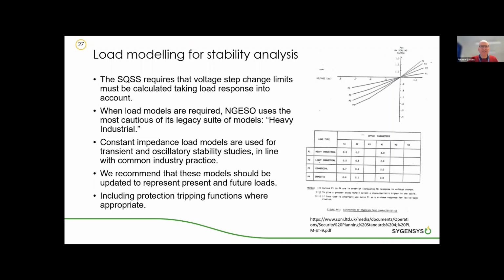In time-domain simulation studies, constant impedance load models are used for both the transient and oscillatory studies, and that's in line with common industry practice. It's much easier algorithmically to study time-domain simulation with constant impedance loads. But we do recommend that these models for all three types, voltage, transient, and oscillatory stability, should be updated to represent present and then future load types. And also critically to include tripping functions where appropriate. One of the big features of these future loads will be, they will be active loads with their own protection, and that's something we've never had in the past.